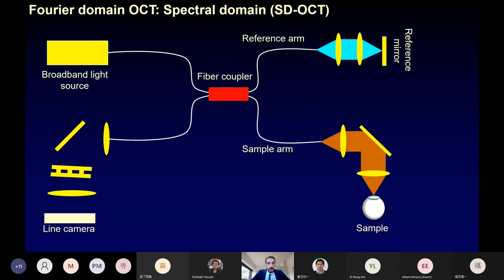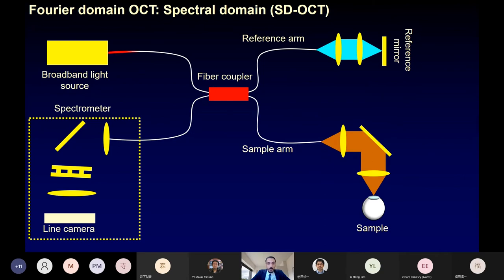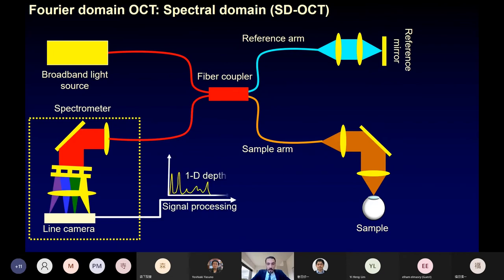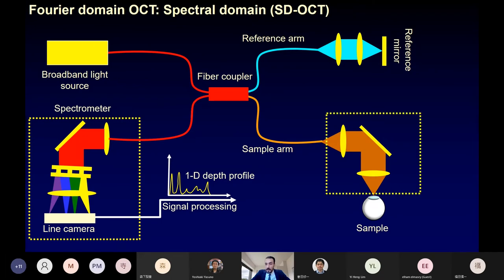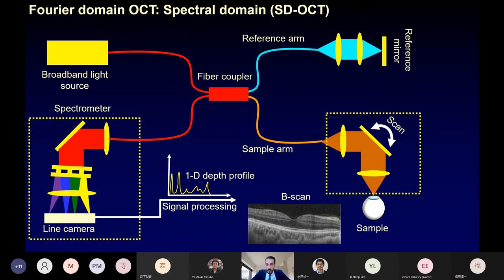Recent OCT devices are Fourier domain OCT, which has two variations. The first is spectral domain OCT, where the light source is a broadband light source and signal detection is done using a high-speed spectrometer. Light is split by a fiber coupler to the reference and sample arm, back-reflected from the reference mirror and the sample, recoupled at the fiber coupler, and the interference signal is detected. By signal analysis, a one-dimensional depth profile is obtained, and by scanning with a mirror in the sample arm, a two-dimensional structural image — called an OCT B-scan — is produced.